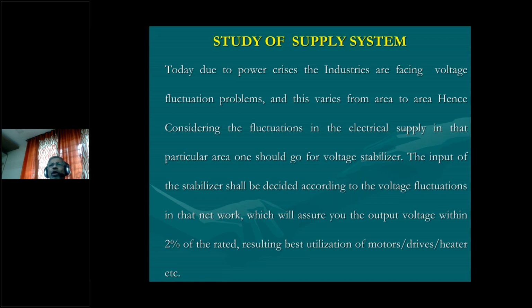Now, if we talk about stabilizers, we have conventional stabilizers, that is, the servo voltage stabilizer. There are two types of stabilizers. One is a balanced type, another is an unbalanced type. What is meant by balanced type? Balanced type means three dimmerstats are mounted on a common shaft. A servo motor is mounted on the common shaft of the three dimmerstats, and with the mean value of the three-phase supply, the RMS value of the three-phase average, they try to correct the voltage.